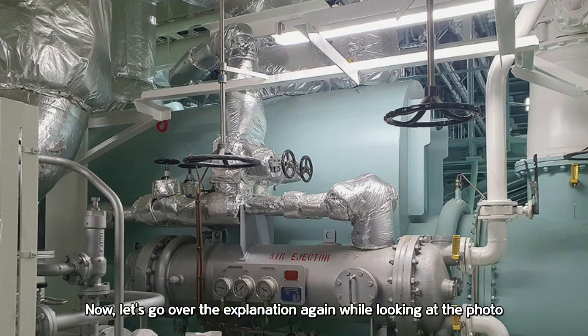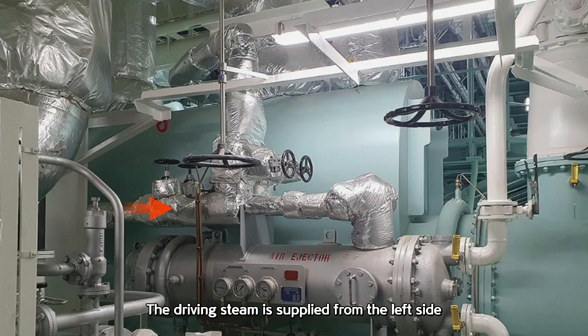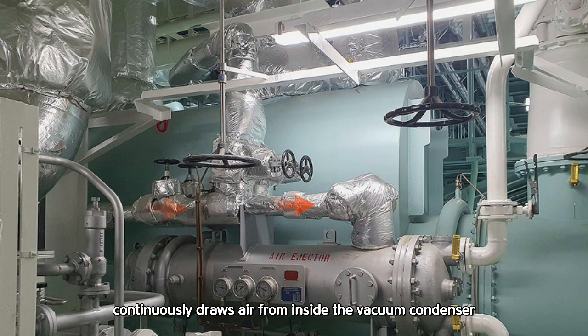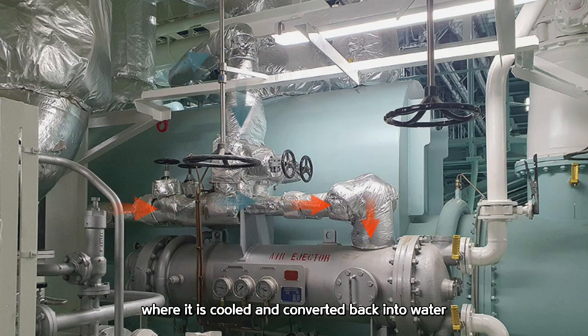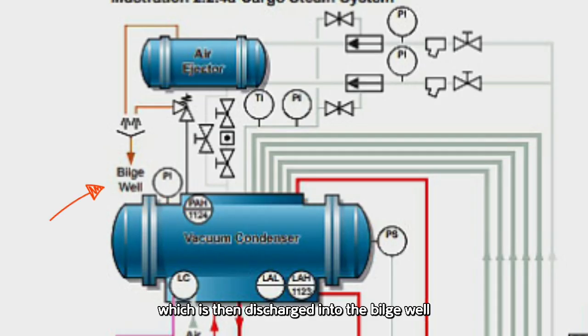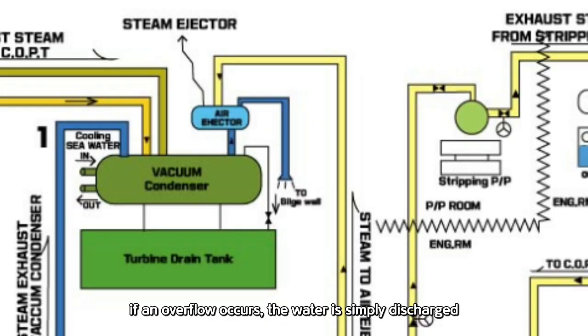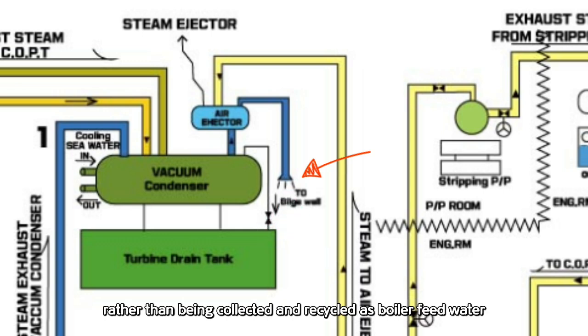Now let's go over the explanation again while looking at the photo. The driving steam is supplied from the left side and exits through the right discharge side. At the same time, the ejector suction section continuously draws air from inside the vacuum condenser. After completing its function, the steam passes through the ejector condenser, where it is cooled and converted back into water, which is then discharged into the bilge well. Since the amount of steam consumed by the steam ejector is not very large, if an overflow occurs, the water is simply discharged rather than being collected and recycled as boiler feed water.